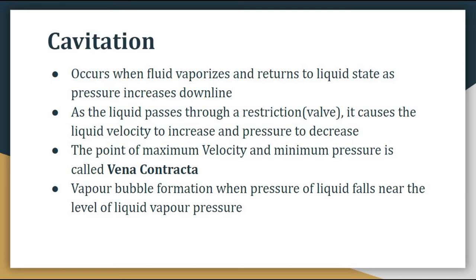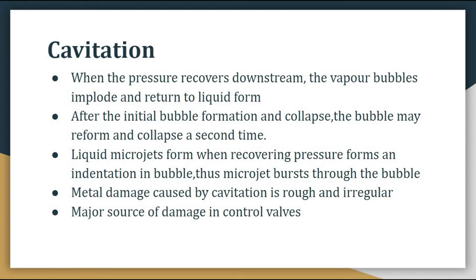Vapor bubble formation occurs when the pressure of the liquid falls near the level of liquid vapor pressure — this is known as cavitation. When the pressure recovers downstream, the vapor bubbles implode and return to liquid form. After the initial bubble formation and collapse, the bubble may reform and collapse a second time. Liquid micro jets form when the recovering pressure forms an indentation in the bubble, and the micro jets burst through the bubble. After bubble formation, metal damage occurs.